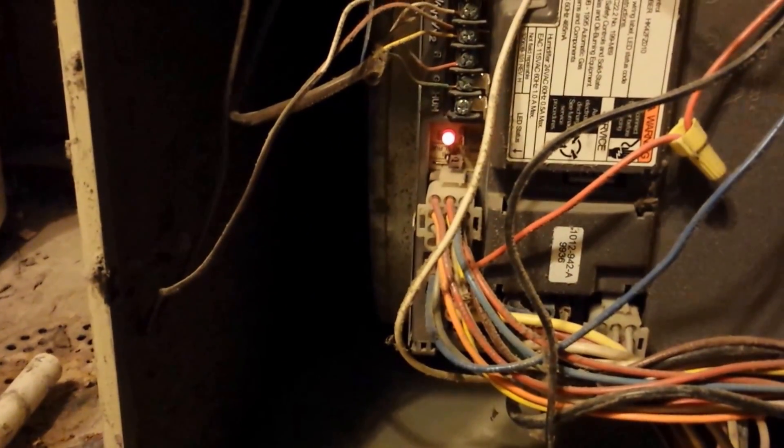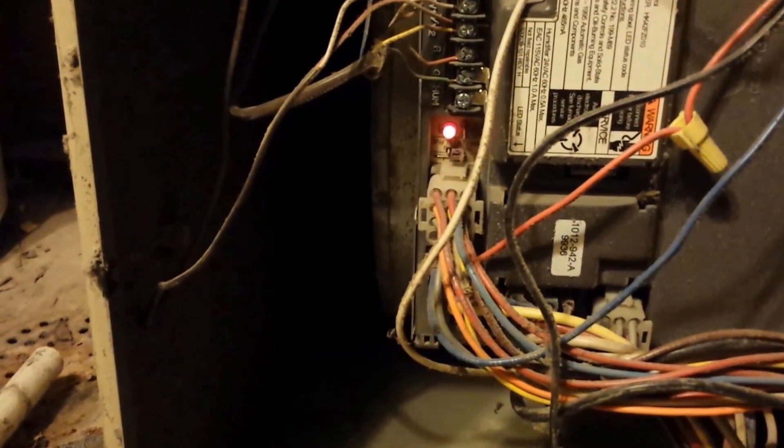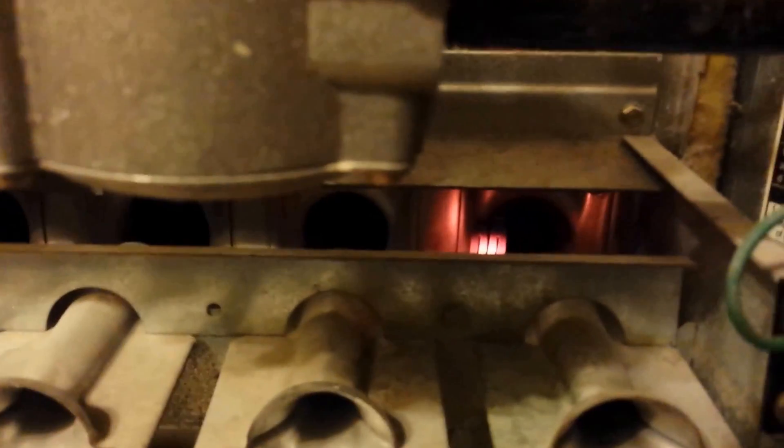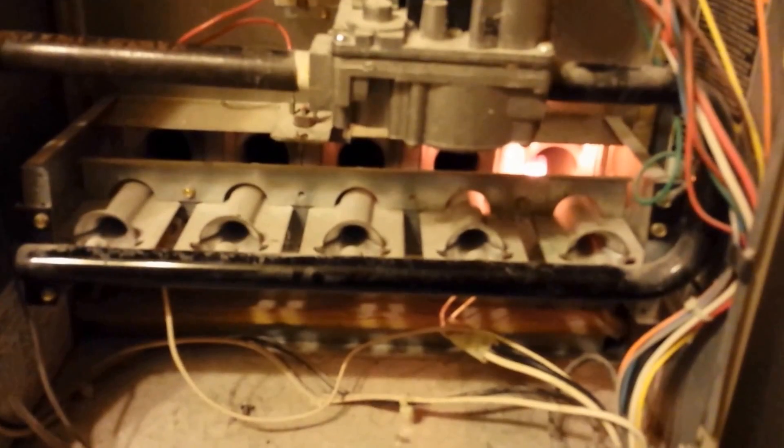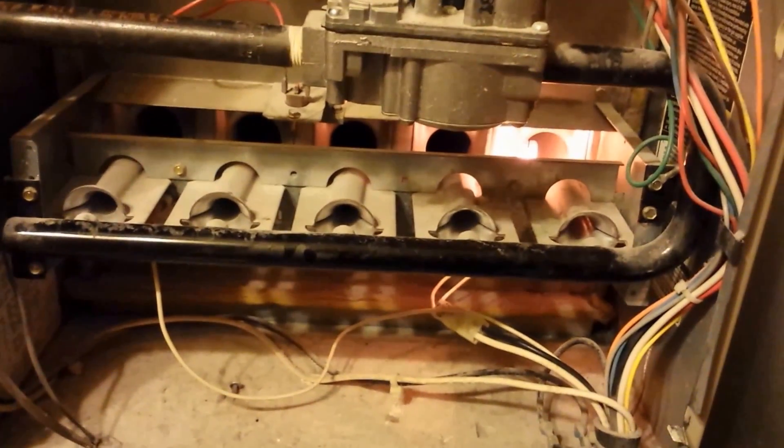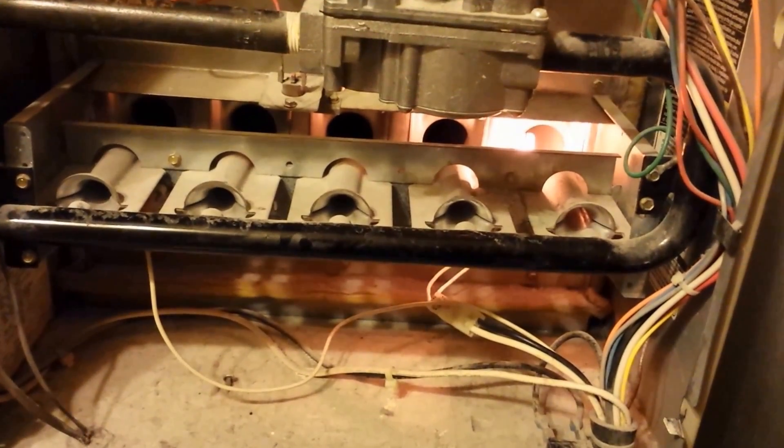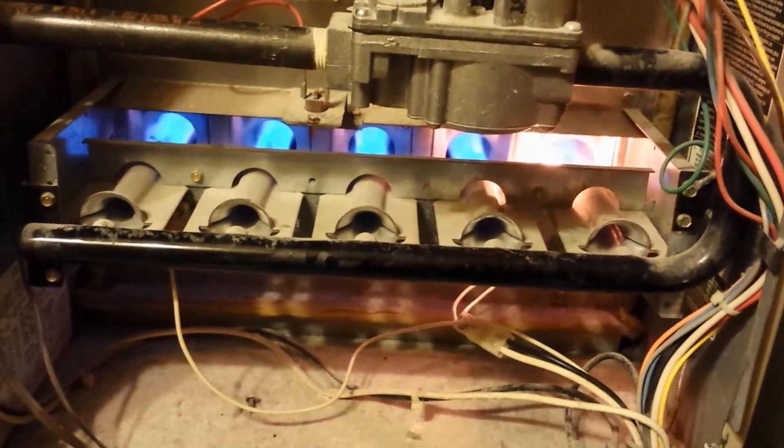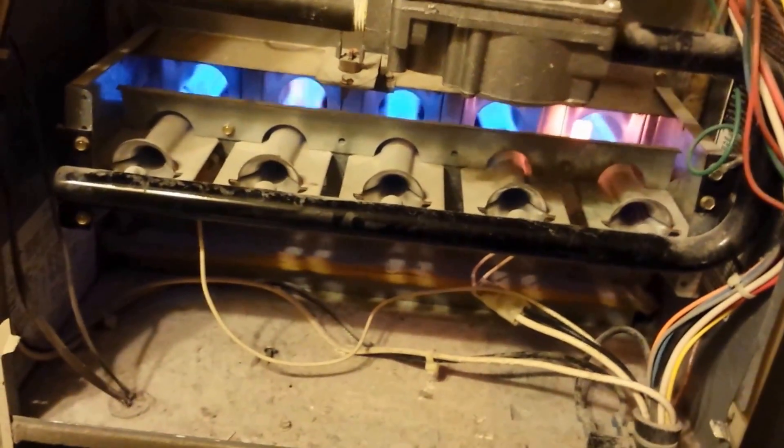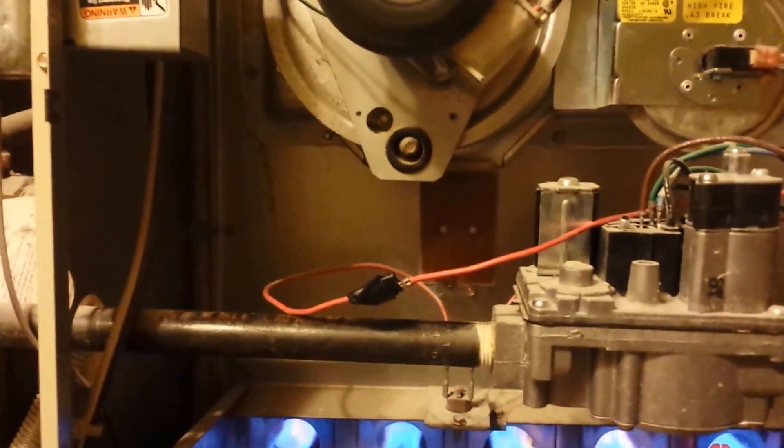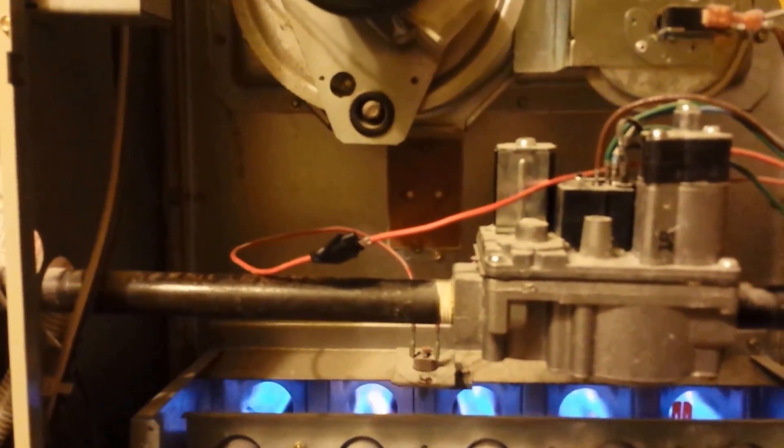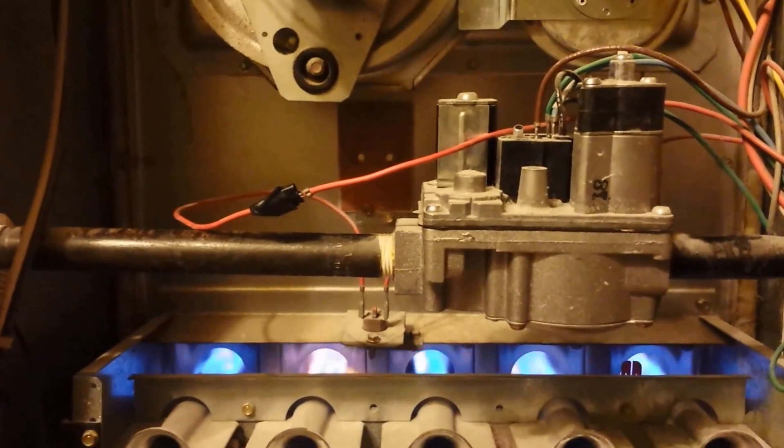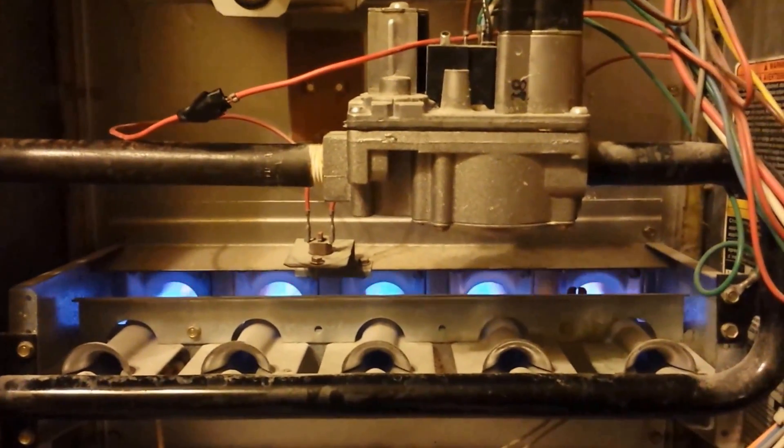One nice thing too is the indicator light. The light is solid, which means no problems. And now we've got the igniter coming on. We'll see gas. This jet's going to ignite. That is a happy, happy sight after two cold nights, Christmas Eve and Christmas Day. Happy fixing and hope this helps you to resolve your problem with your furnace.